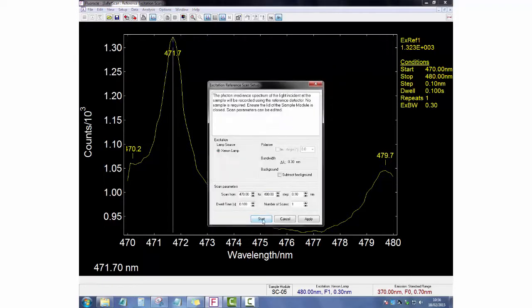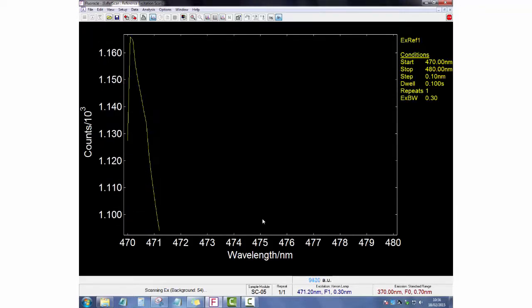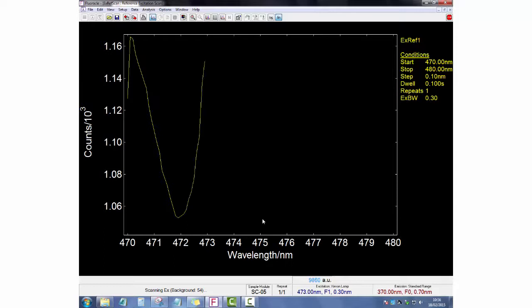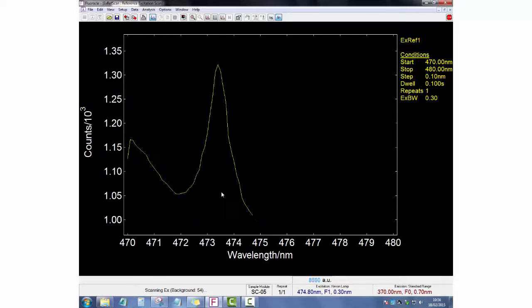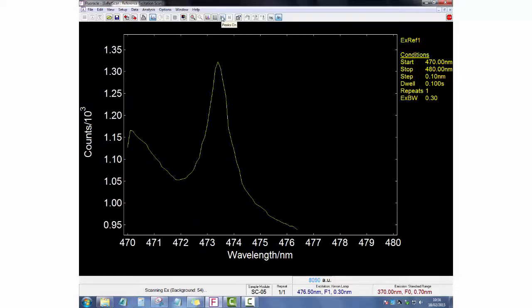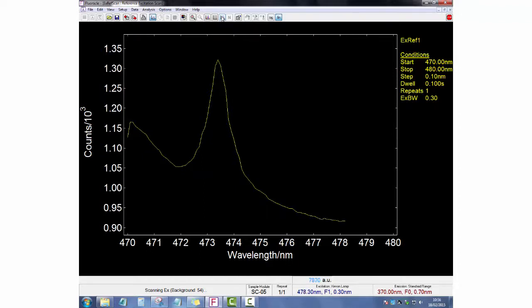You can then repeat the scan to ensure that the line position has moved. This will update the calibration settings of the excitation monochromator to ensure that the line is now in its correct position.